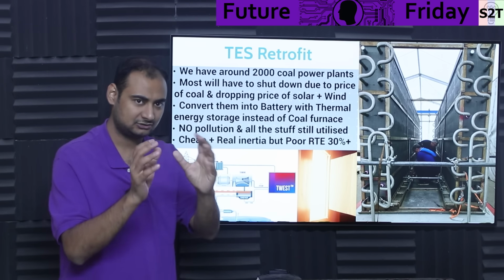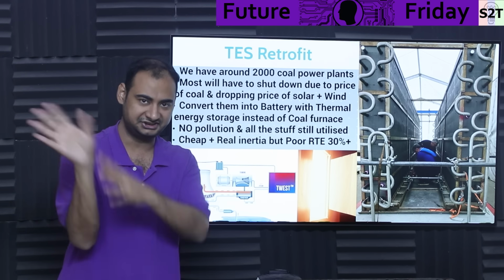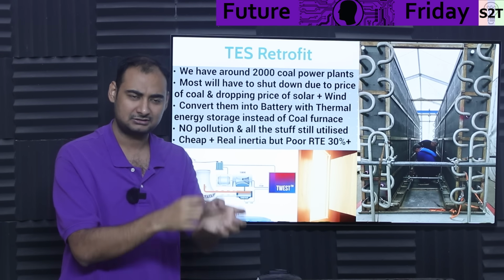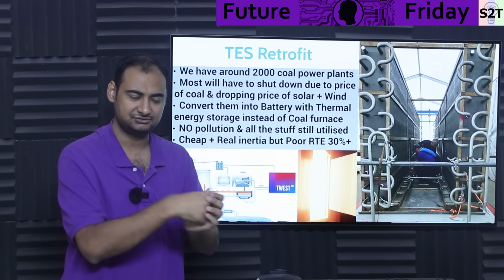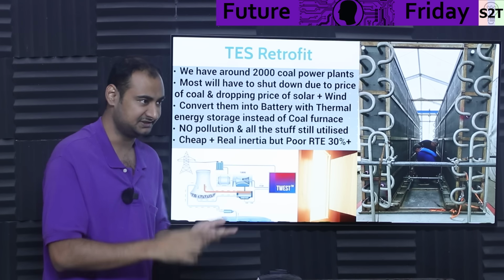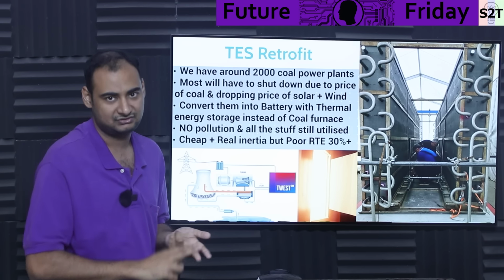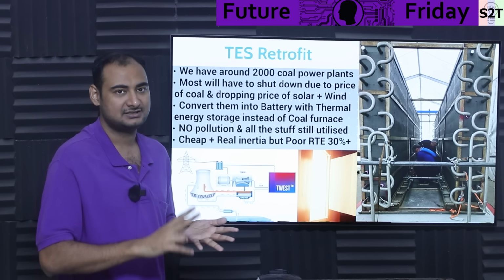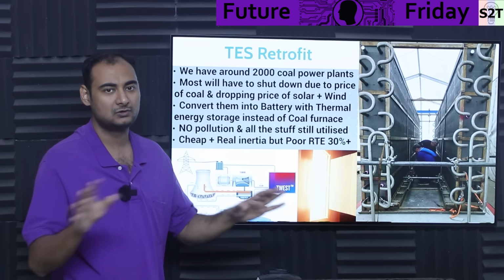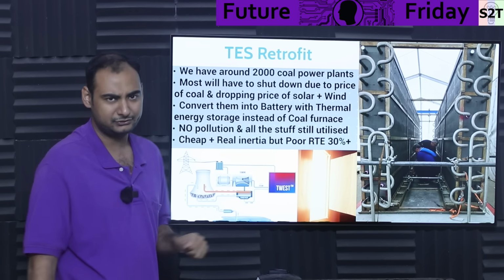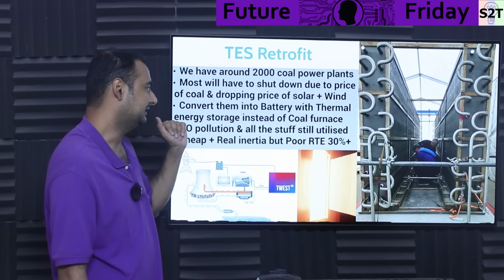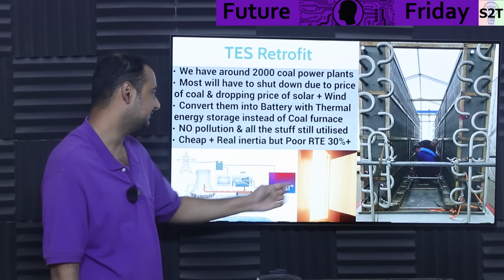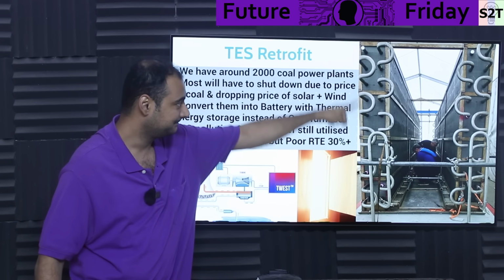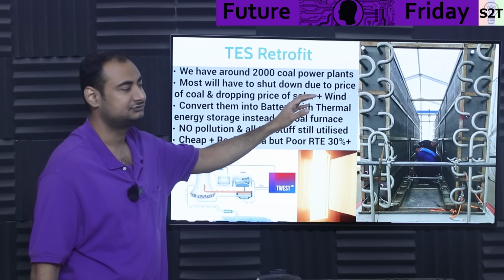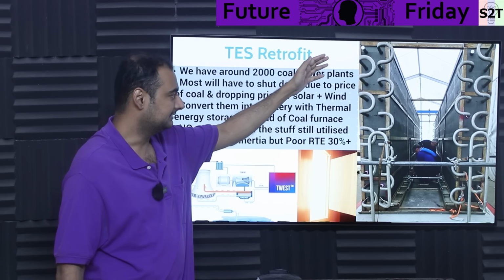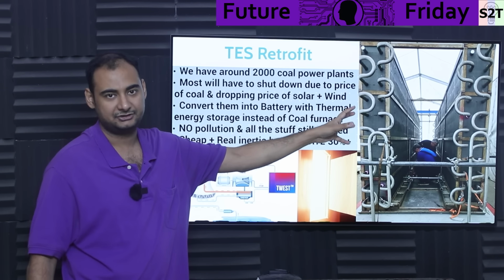How would you do that? You take the coal section, the coal storage, yeet that. The coal crusher, yeet that. The furnace, yeet that. Then you keep everything else: the wiring, the substation, the control mechanism, the SCADA system, basically the whole steam cycle including the cooling tower. You keep all of that, and instead of a coal furnace, you have this graphite block. This is from E2S Power, and this graphite block has the ability to store energy.